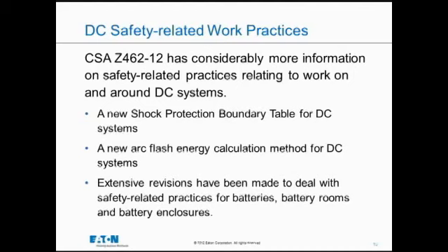The 2012 standard has come up with information with regards to direct current. There was no information in 2008 on how to calculate arc flash for DC. And so we've got new tables and new equations for calculating DC for situations like batteries, battery rooms. Nuclear power plants use a lot of DC for their backup power. So there's quite a number of locations that can now use the DC equation. So that's something new inside the Best Practice Guide.